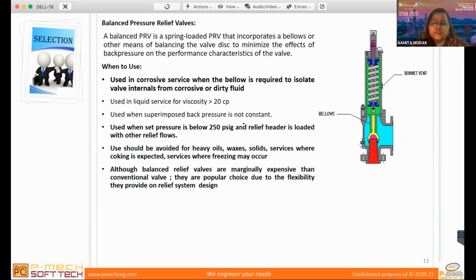They have a lot of good advantages, like you can use them in corrosive service, because the bellows isolates the valve internals from the corrosive, dirty fluid. So that is the advantage. But when you have a viscosity greater than 20 cP, you should avoid using it in heavy oil, waxes, solid services, and coking, because it can choke the bellows, and freezing may also occur where you are expecting hydrate-type services. Similarly, for pilot-operated valves also, you have to avoid these services because it will basically choke these PSVs.